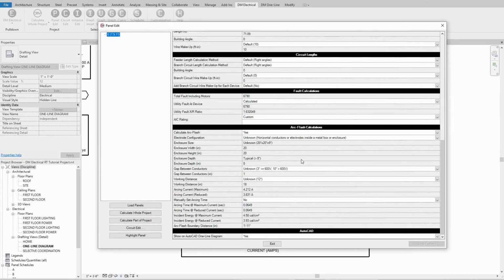So at the bottom of your panel edit, we have all the arc flash calculation settings. To do arc flash, you need a little bit of additional information about the actual configuration, like how it's physically put together. You put all that information down here. It eventually calculates an arcing current. And then from the arcing current, you use these curves to calculate the arcing time.